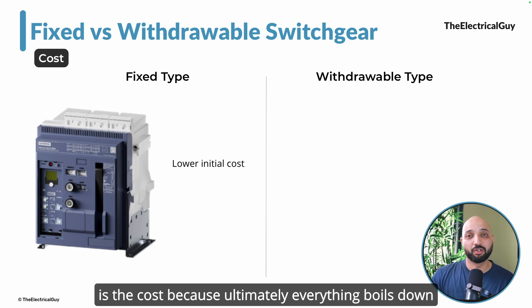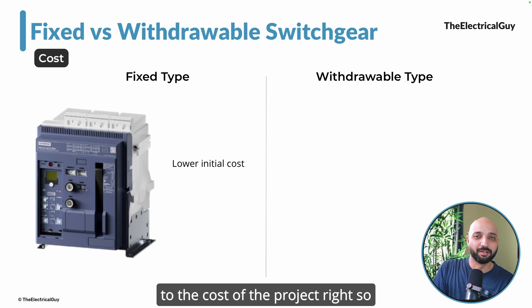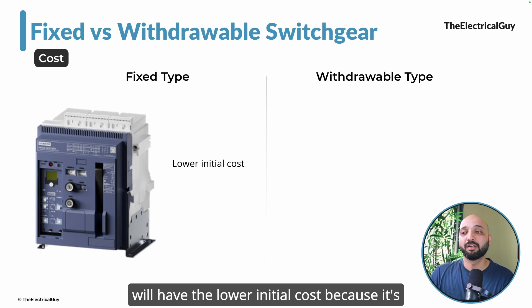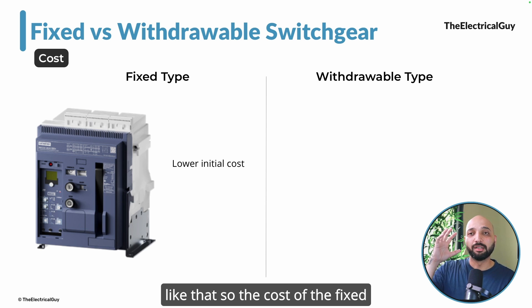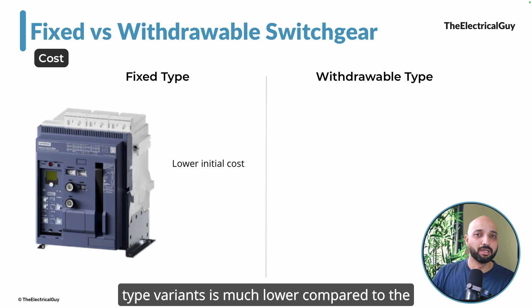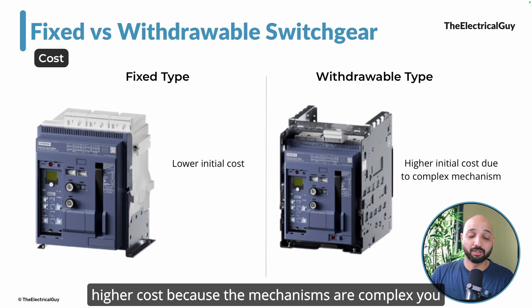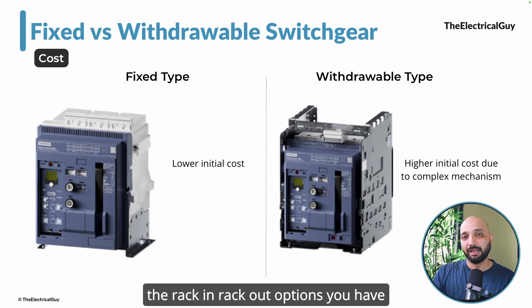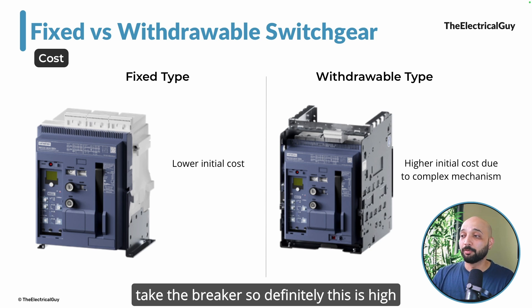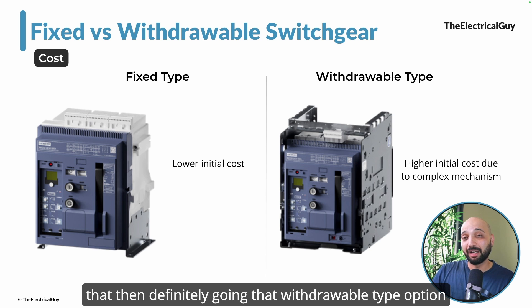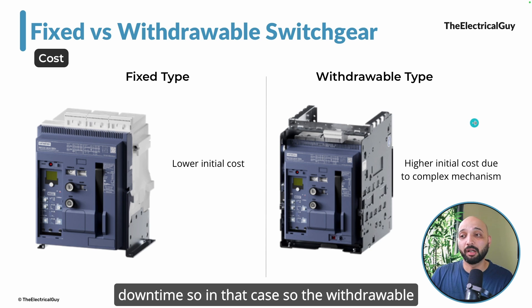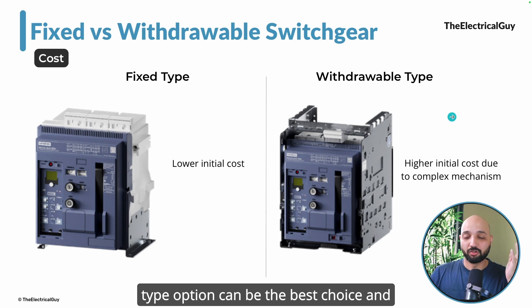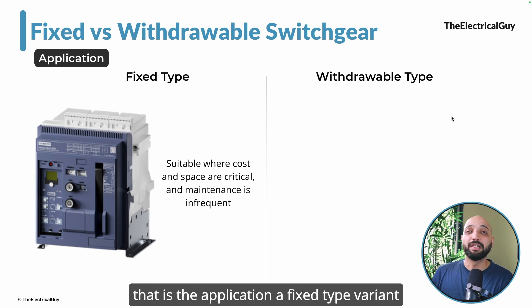The most important point is cost. The fixed type has a lower initial cost because it is simple in construction with no complicated moving parts or interlocks. The withdrawable type has a higher cost due to complex mechanisms, interlocks, rack in and rack out options, and the trucks needed to move the breaker. However, if your project demands it — if you cannot afford shutdowns or long downtimes — then the higher cost of withdrawable type makes sense.